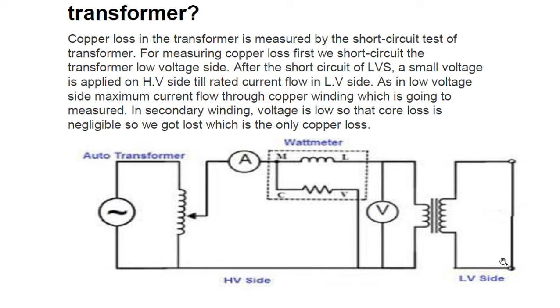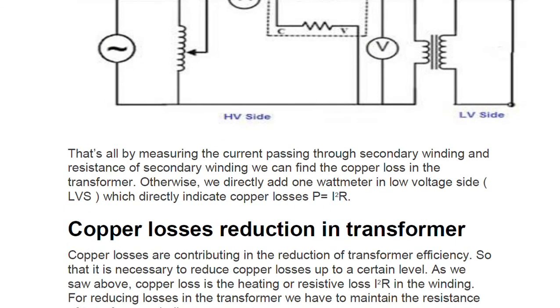We apply voltage to the HV side until the LV side reaches its rated current. As the maximum current flows through the copper winding on the low voltage side, this current is measured. In the secondary winding the voltage is low, so core loss is negligible. Therefore, the loss we measure here is essentially only the copper loss.